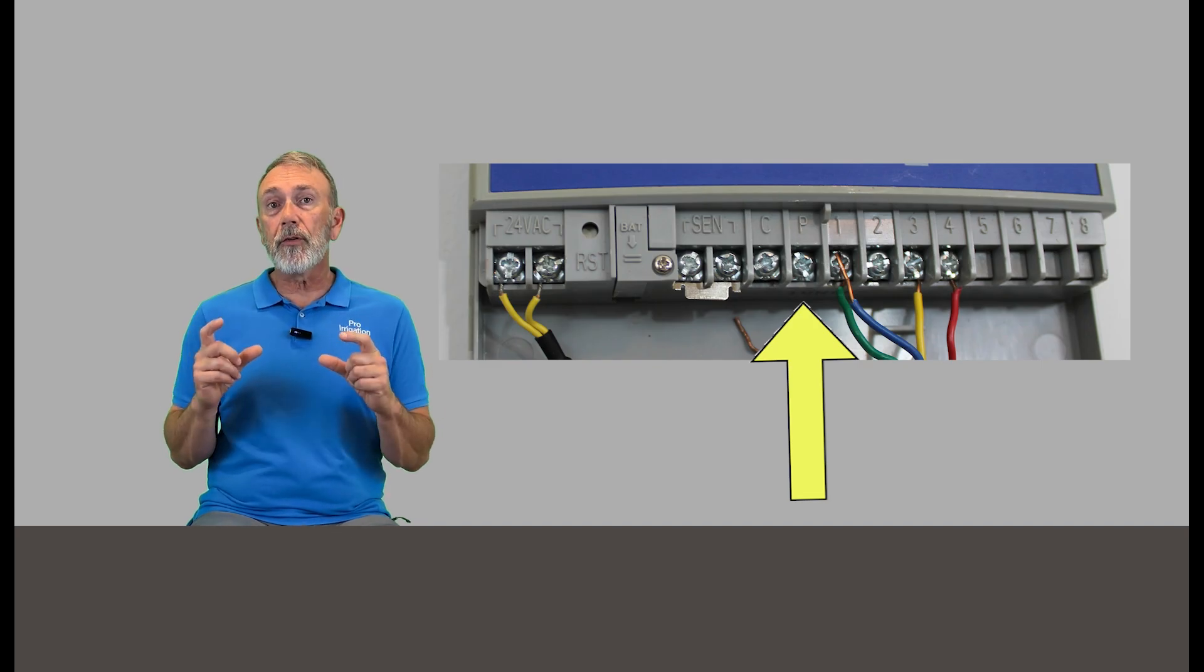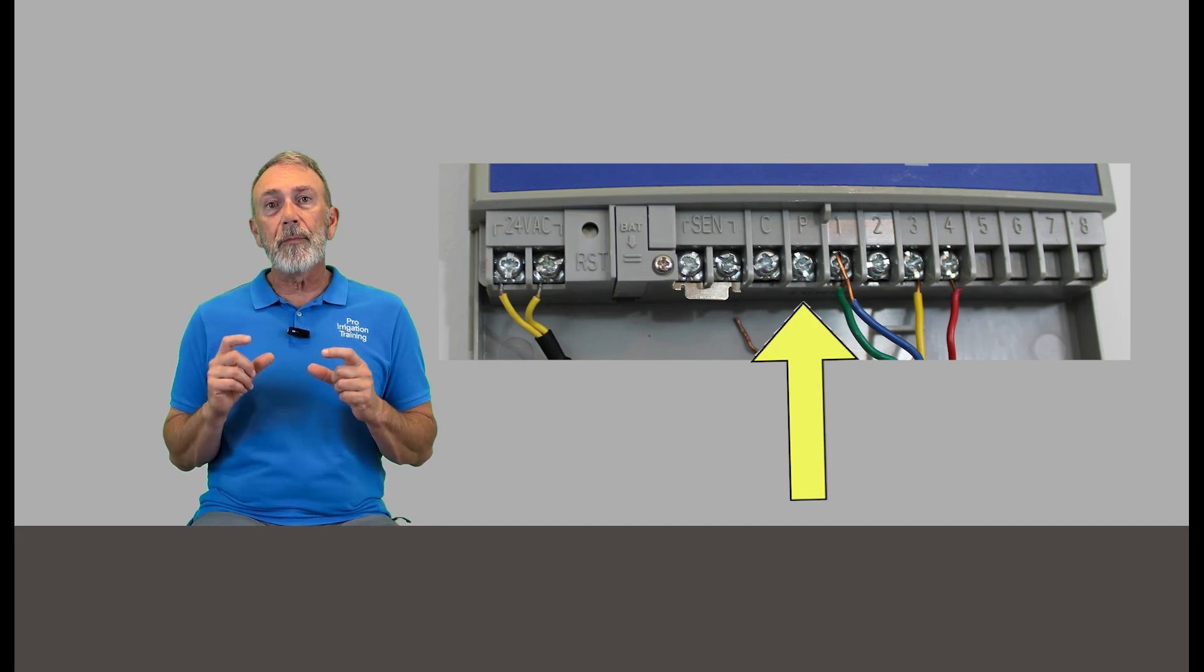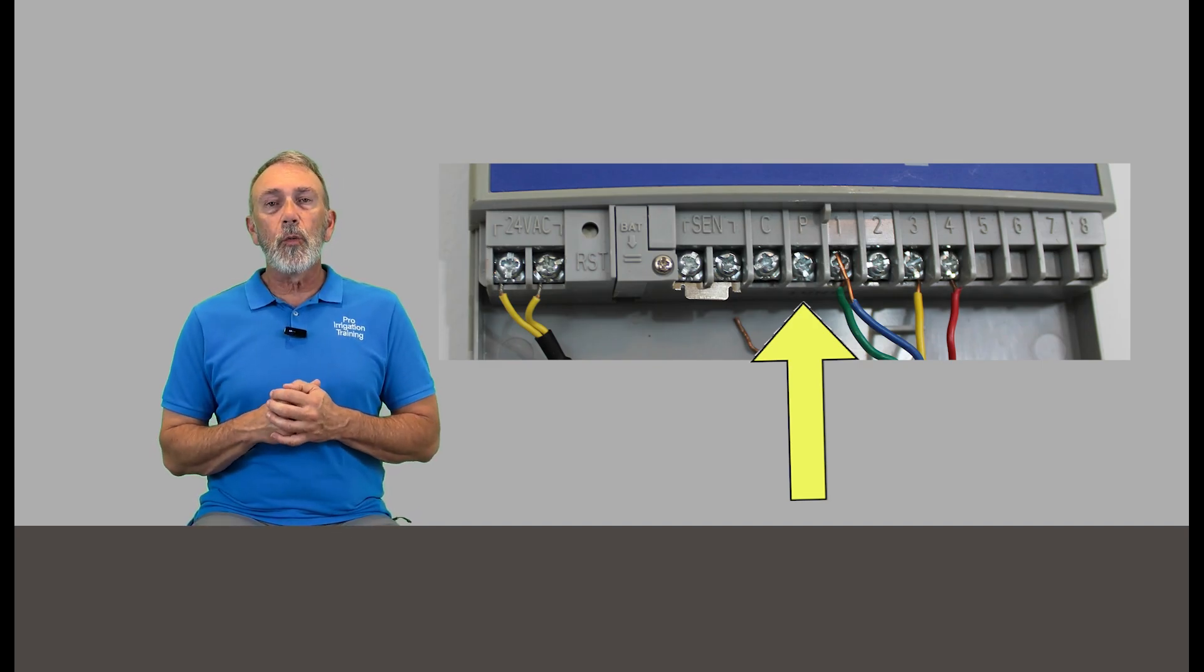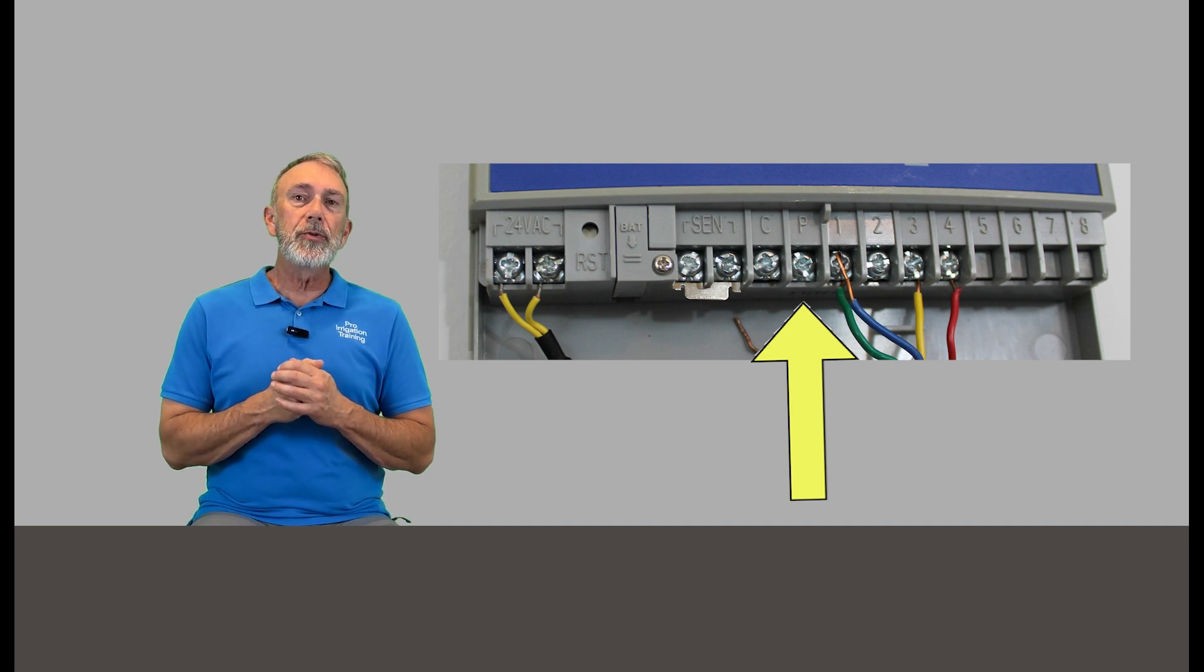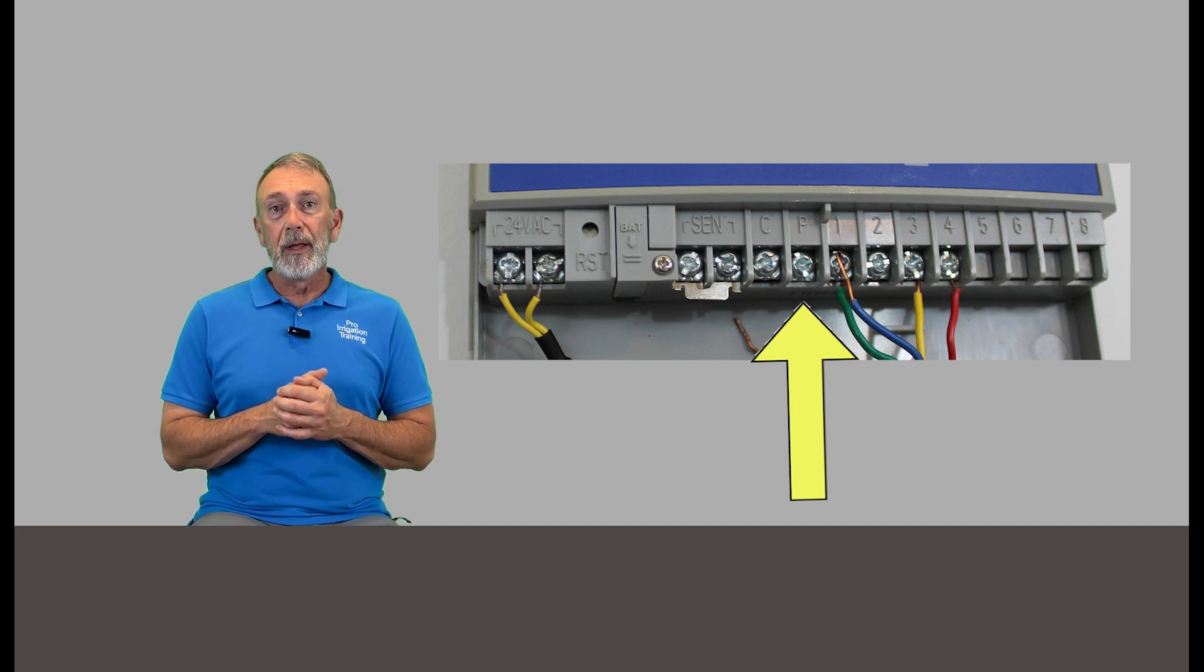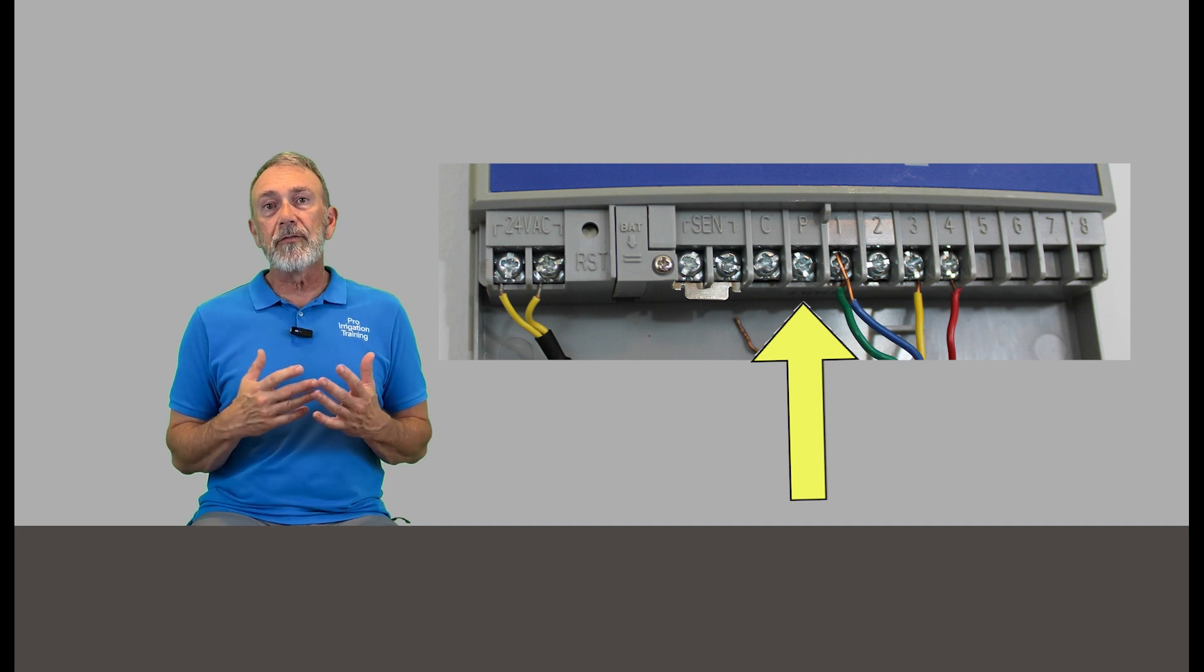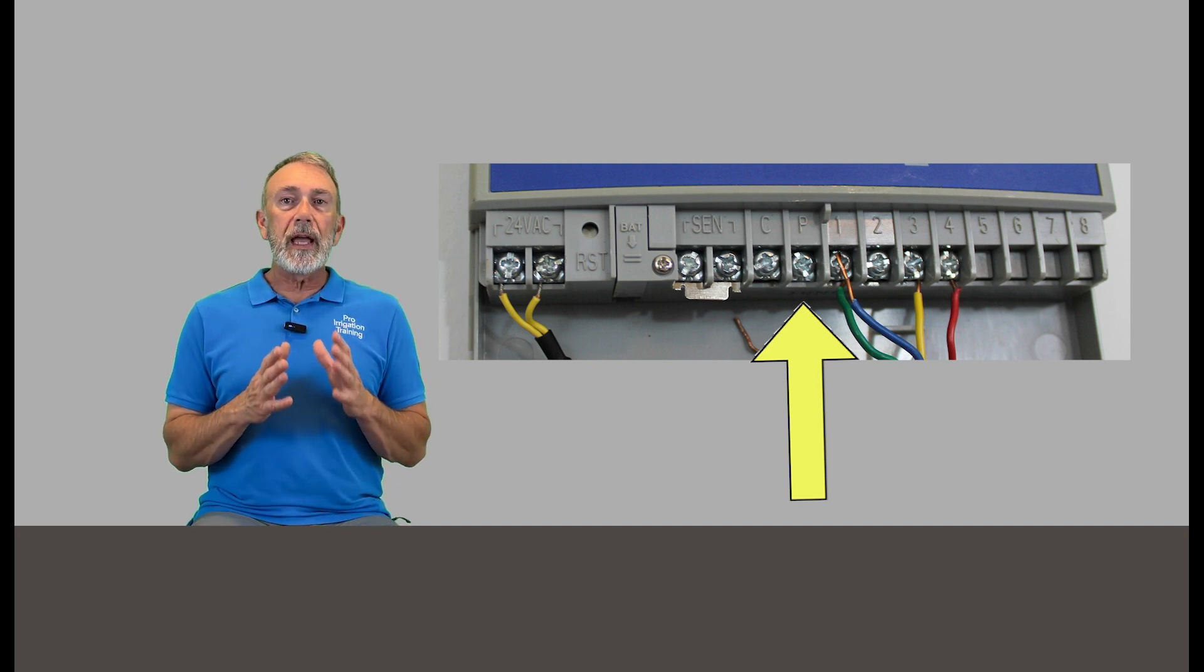Now we're going to take the bottom cover off of our timer and look to see if there's a wire screwed into the terminal marked P or M. That stands for pump or master valve, and what that is is a way for the timer to turn on an external device at the same time it's turning on the irrigation system and opening up valves.